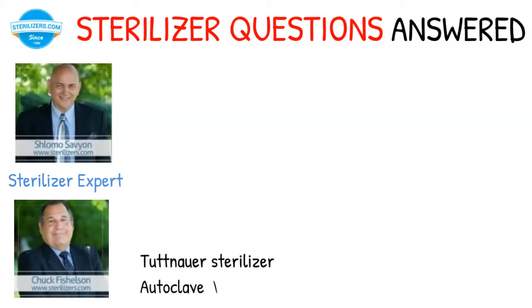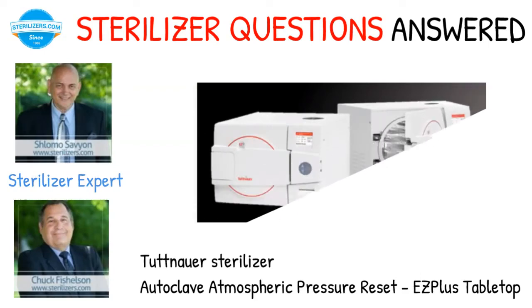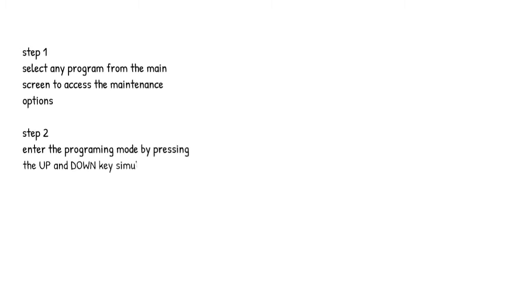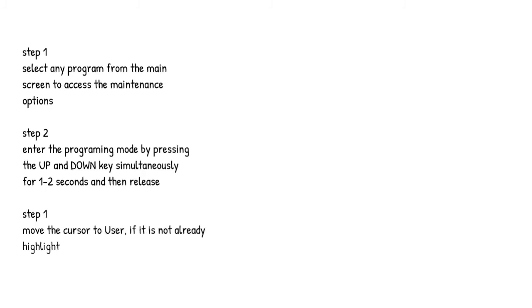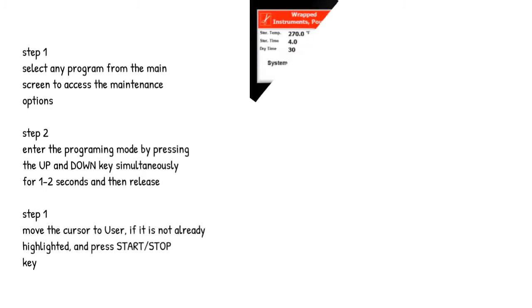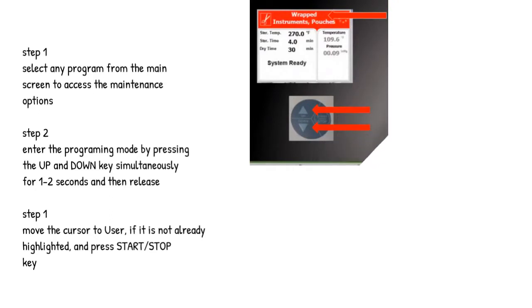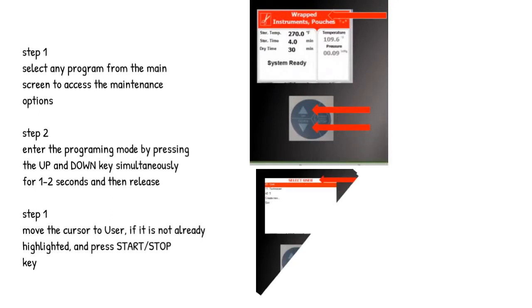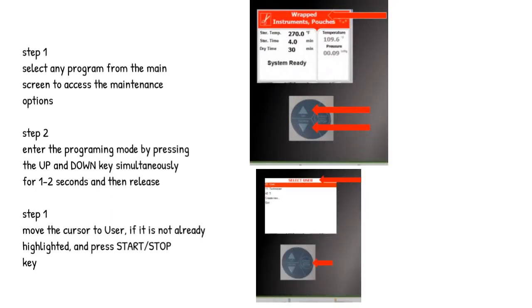Sterilizer questions answered. Tuttnauer sterilizer autoclave atmospheric pressure reset, EZPlus Tabletop. Step 1. Select any program from the main screen to access the maintenance options. Step 2. Enter the programming mode by pressing the up and down key simultaneously for 1 to 2 seconds and release. Step 1. Move the cursor to user, if it is not already highlighted, and press start/stop key.